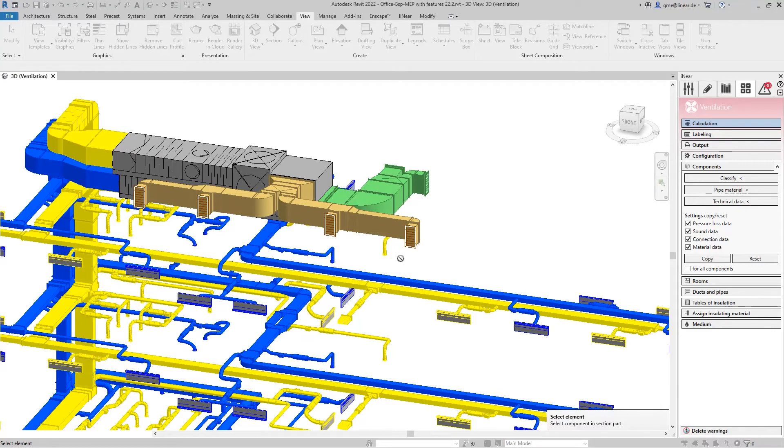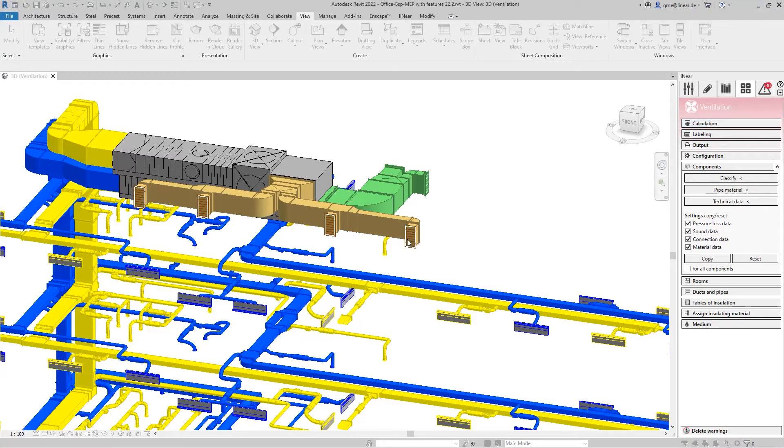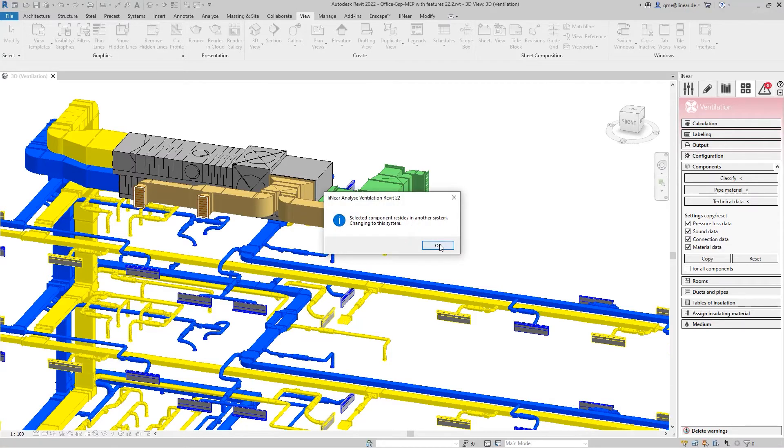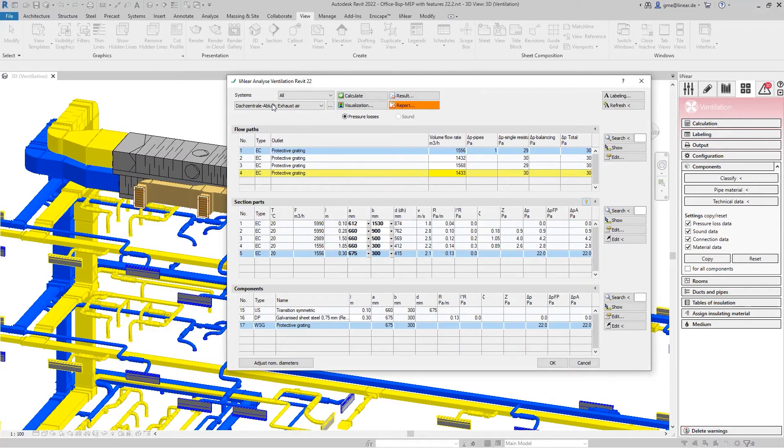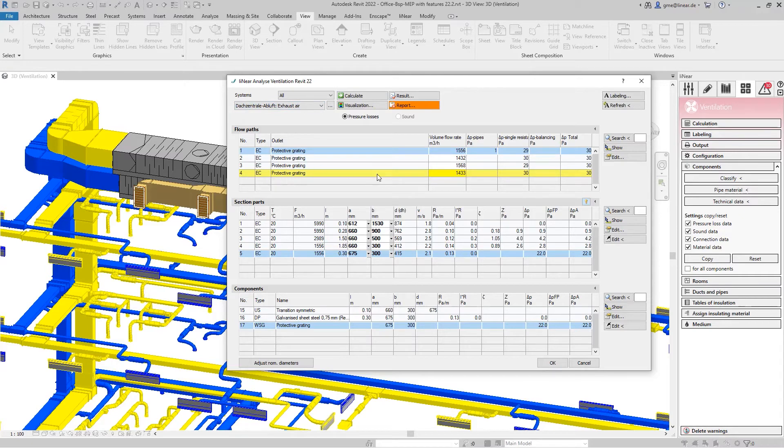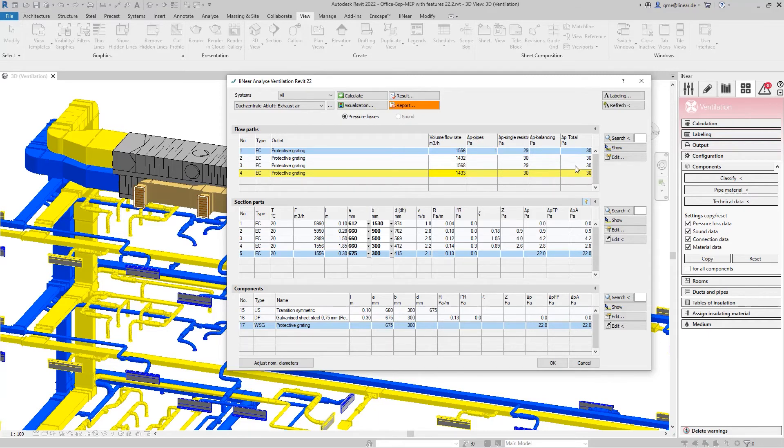So if we search for the grate, the system switches to exhaust air, and we also see that despite identical grate sizes, the total air volume flow is distributed depending on the individual flow path with their individual fitting parts. And at the end, each flow path has the same total pressure loss of 30 Pa.